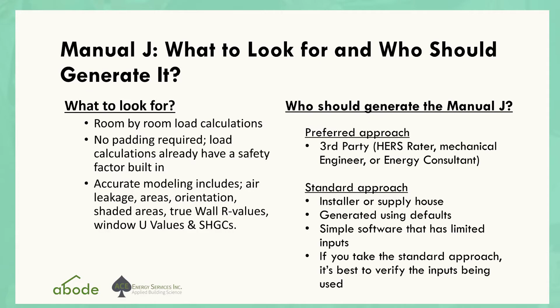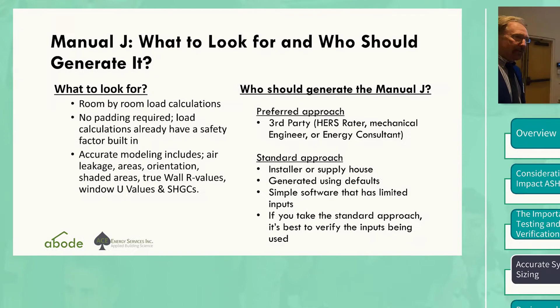So what to look for in a Manual J: room by room load calcs, no padding required, since load calculations already have a safety factor built in. That's true, all the software kind of has a little safety factor built in. Accurate modeling includes air leakage - these are the things I've been talking about - air leakage areas, orientation, shaded areas, true R values, and of course, window U values and solar heat gain coefficients.